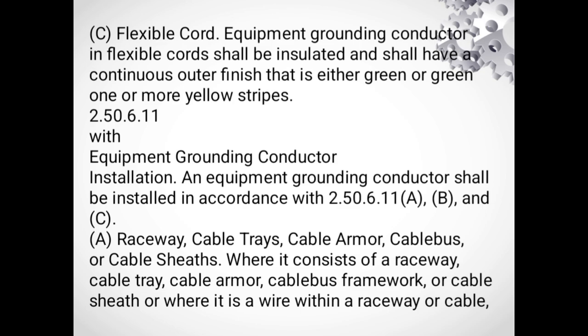C. Flexible cord. Equipment grounding conductor in flexible cord shall be insulated and shall have a continuous outer finish that is either green or green with one or more yellow stripes. 2.50.6.11 Equipment grounding conductor installation. An equipment grounding conductor shall be installed in accordance with 2.50.6.11 A, B and C.